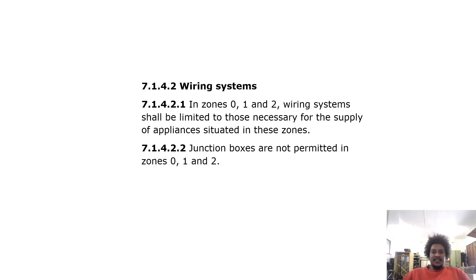Wiring systems in zones 0, 1 and 2: wiring systems shall be limited to those necessary for the supply of appliances situated in these zones. Junction boxes and trunking boxes are not permitted in zones 0, 1 and 2.